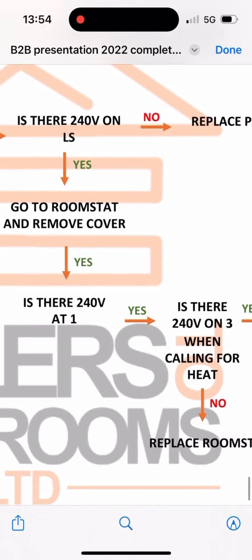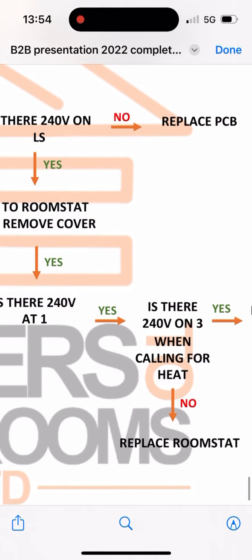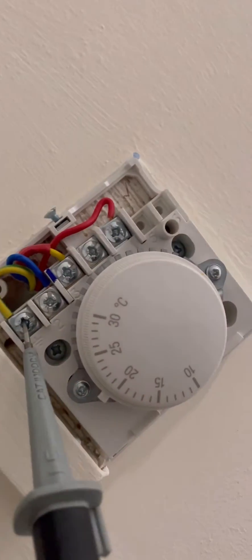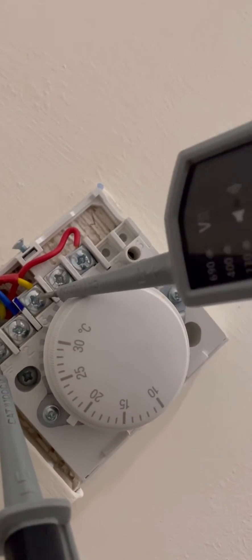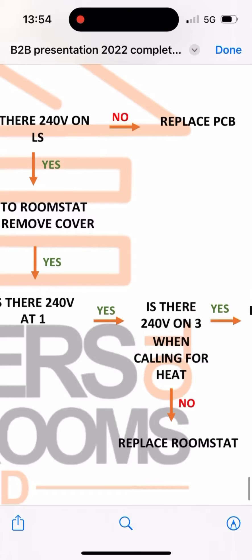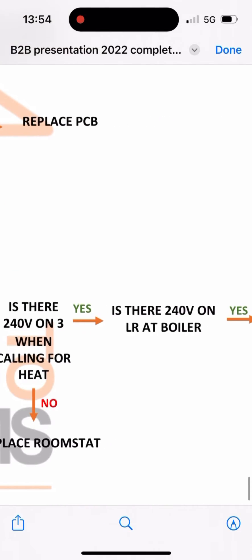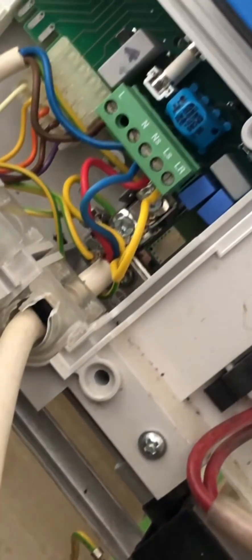Go to the room stat, remove the cover. Is there 240 on terminal one? Yeah. Is there 240 on terminal three? There's not at the moment - turn the room stat up. Should be 240 now to prove the room stat's fine. Is there 240 on LR at the boiler, just to check the cable's not broken? Yeah, 240 on LR.